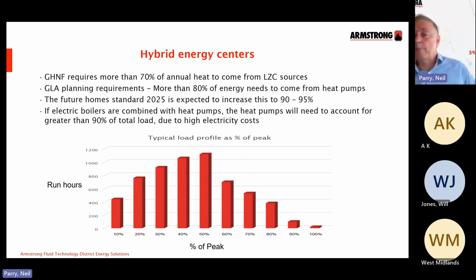So when we look at those hybrid energy centres where we are integrating heat pumps, then we know the Green Heat Network Fund requires more than 70%, excuse me, of annual heat to come from low to zero carbon sources. The Future Home Standard is expected to increase that to around 90 to 95%. But what we've got to remember here is that load profile and run hours of a typical system. What we see is the vast majority of the time, the demand is much, much lower than peak, and it's around about 50% or less for the majority of time.